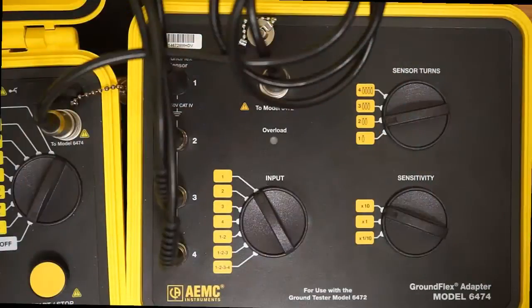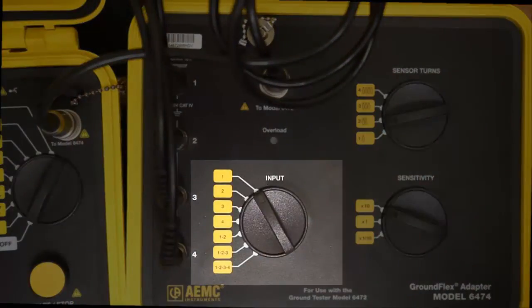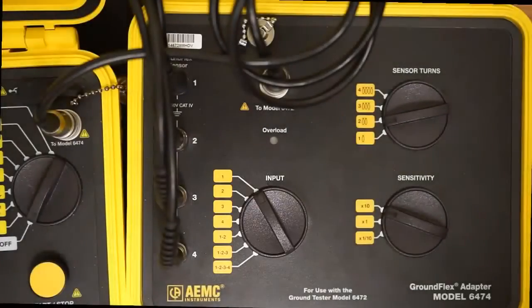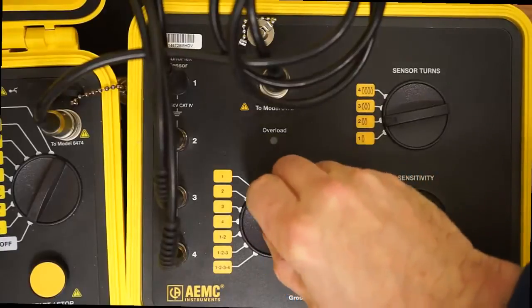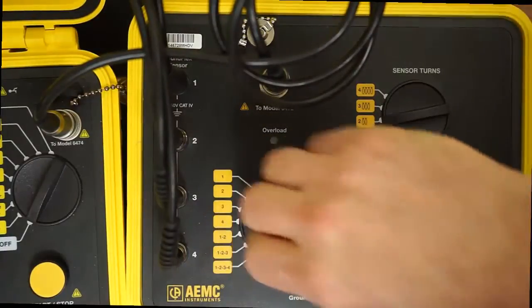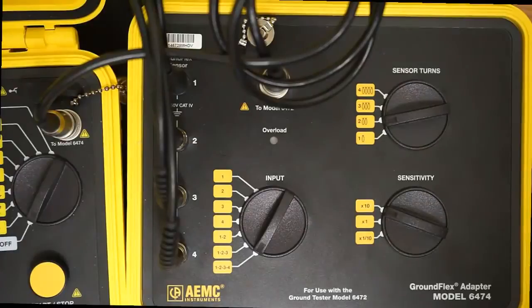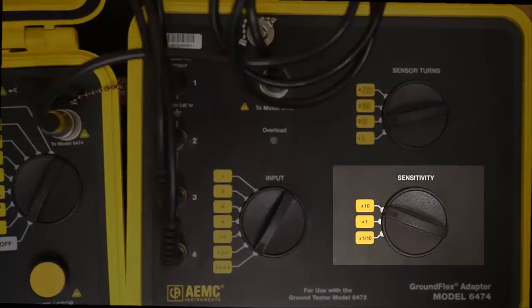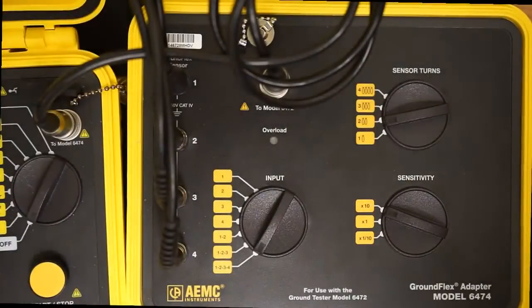Next, set the input dial on the Model 6474. This indicates which tower leg or legs you want to test. In this instance, we would test all 4 legs together, so turn the dial to the 1, 2, 3, 4 setting. Finally, set the sensitivity dial on the instrument to 1 to establish measurement sensitivity.